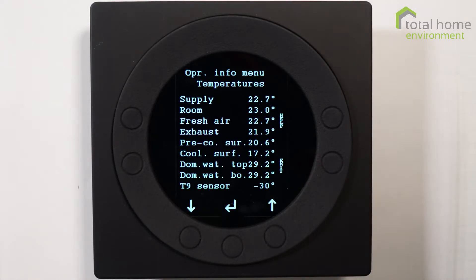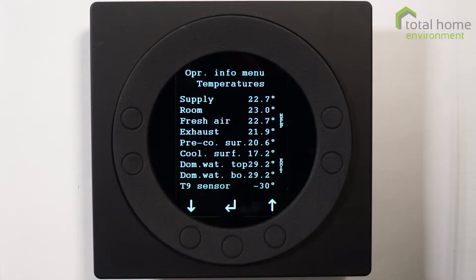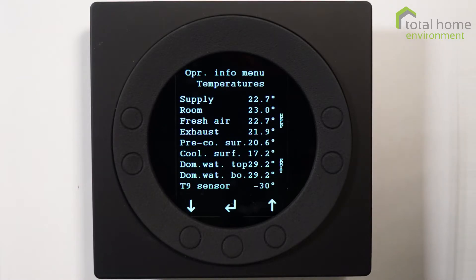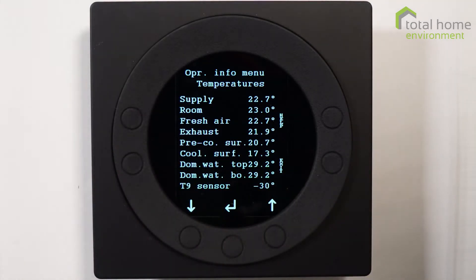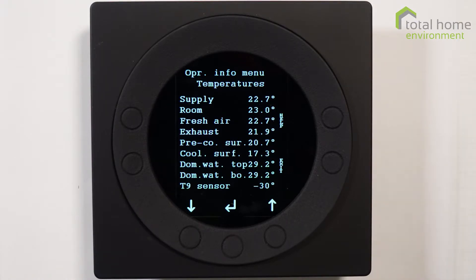The first screen that you see gives us all the temperatures that are going on the machine. Remember this is a snapshot of what's happening and it will change every 20 seconds. The device will scan the sensors and will make appropriate changes to those settings. Currently we have a supply temperature at 22.7, which is what we're supplying to your reception rooms through the machine.